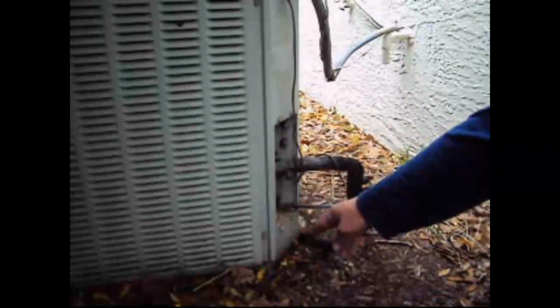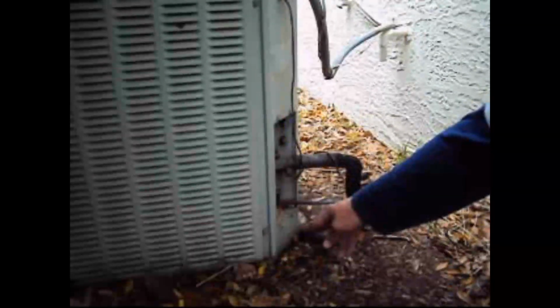To clean it, all you need to do is hook up a vacuum cleaner. It may be black like this, or it may be white PVC. It may have an elbow on the end of it, and if you can take it off, that's fine, but make certain to put it back when you're finished. To clean the drain line, simply hook up a vacuum cleaner like this and turn it on. It would be wise to turn it on and then go inside and make certain that you're pulling air through the drain line.